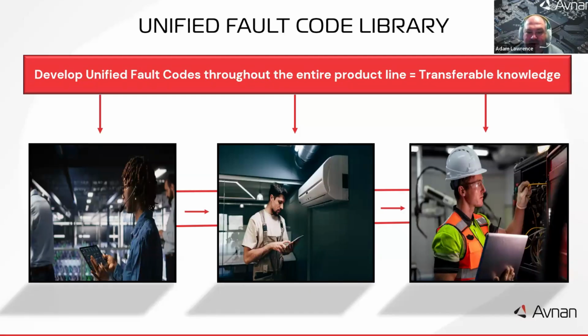By developing a unified fault code library, service teams can interpret fault codes quickly without cross-referencing multiple manuals. A technician who's used to seeing a fault code on one system will immediately recognize it on another. The knowledge transfers instantly across the product line. This will ultimately accelerate troubleshooting and reduce training needs. For the manufacturer, it means your support hotline or service department isn't getting bogged down deciphering codes on different models. It's all standardized, which ultimately improves customer satisfaction.